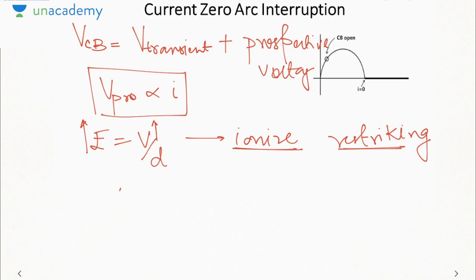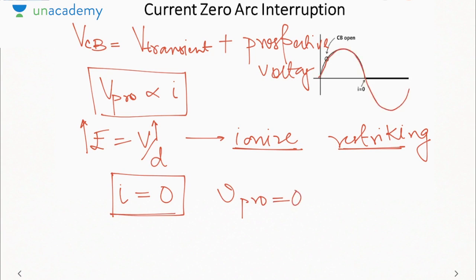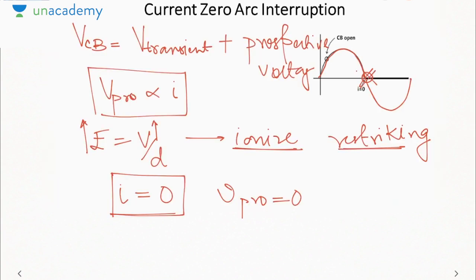We have to ensure interruption happens when current is 0, so that prospective voltage becomes 0. In a sinusoidal waveform, current always passes through 0 after every half cycle, so we interrupt at that point. That is why arc can exist only for 1 or 2 half cycles. We deal in terms of half cycles because we interrupt the arc when current goes through 0, so prospective voltage does not appear and arc does not restrike.